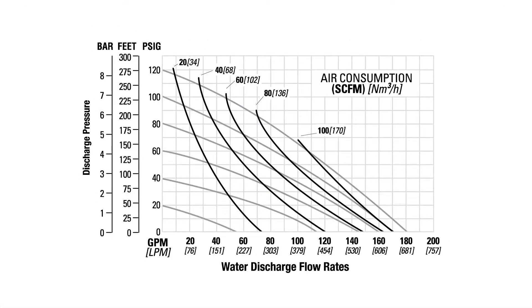Generally, whether pumping a liquid similar to water or something much more viscous, it is recommended to always operate an AODD pump in the center of its performance curve rather than in extreme conditions. This is the most efficient way to operate an AODD pump, not only from a performance and air consumption perspective, but it also helps extend the life of wear parts.